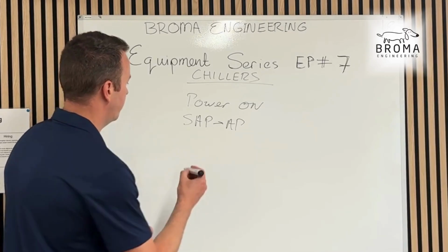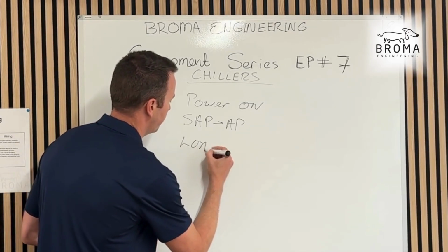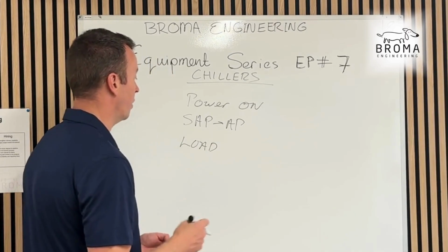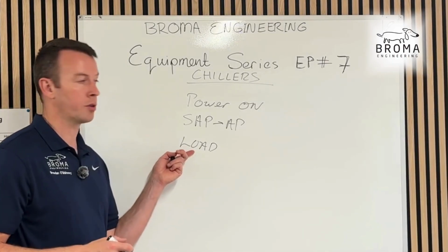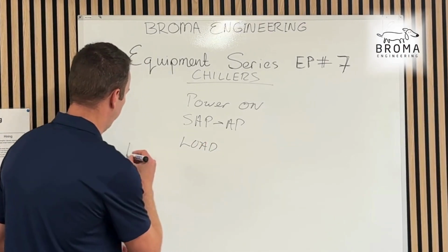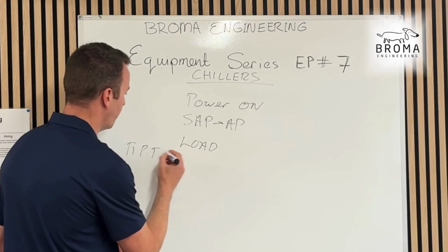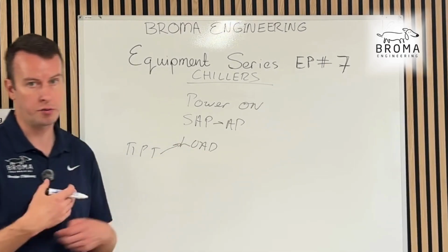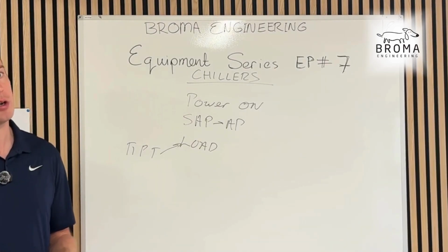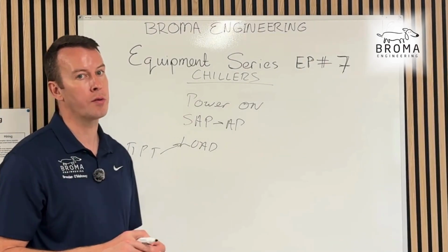And then you'll have to do your load testing. This is more and more going to level 3. I don't think load testing is level 3, by the way, because that is FPT. That's functional performance testing, load testing. That's technically what it is. So really load testing shouldn't be done till level 4.